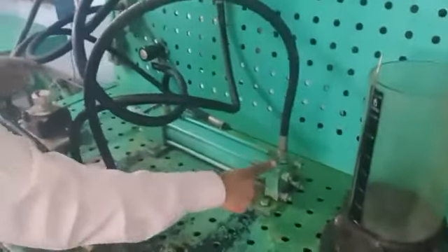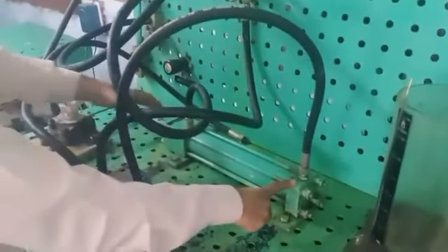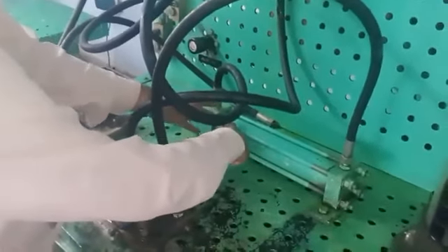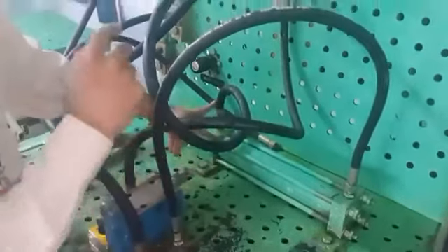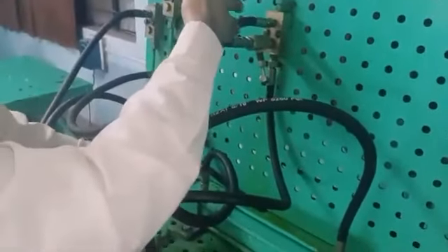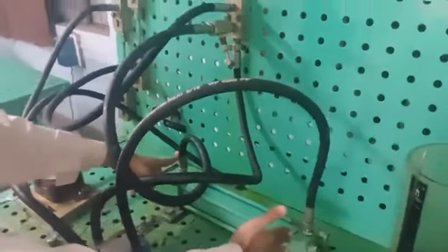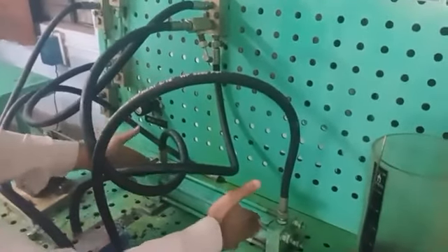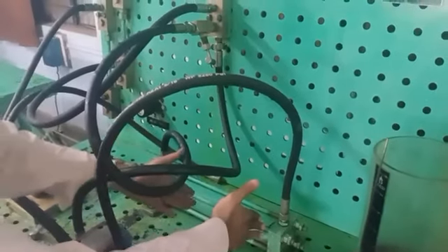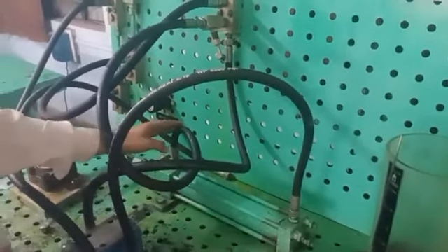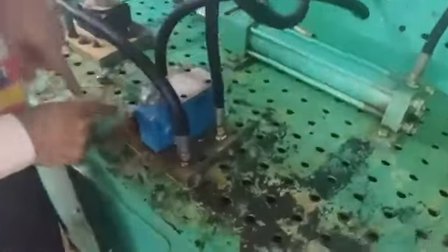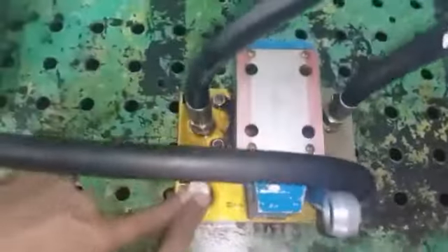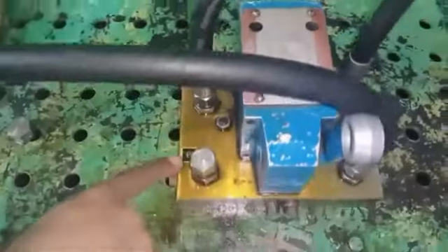Okay, now the A port or the actuator port of the valve is connected to the cap end side of the double acting actuator. Now in regenerative circuit we know that the fluid which is there at the rod end side of the actuator is again fed to the flow of the pump in order to increase the discharge on the cap end side of the actuator, because of which the forward stroke will be much faster than the reverse stroke. So you could see that one port of this particular valve, the B port, is blocked actually.